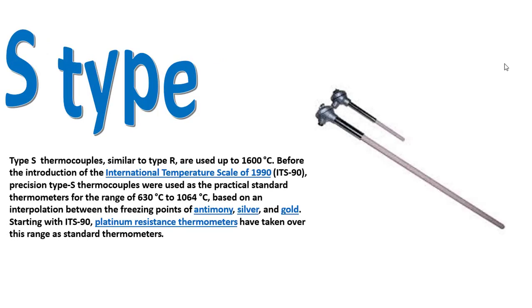Type S thermocouples, similar to Type R, are used up to 1600°C. Before the introduction of the International Temperature Scale of 1990 (ITS-90), precision Type S thermocouples were used as the practical standard thermocouples for the range of 630°C to 1064°C, based on interpolation between the freezing points of antimony, silver, and gold. Since ITS-90, platinum resistance thermometers have taken over these ranges as the standard thermometers.